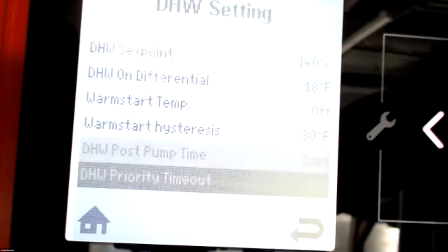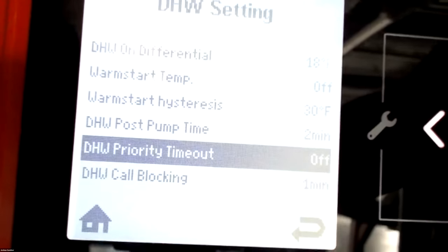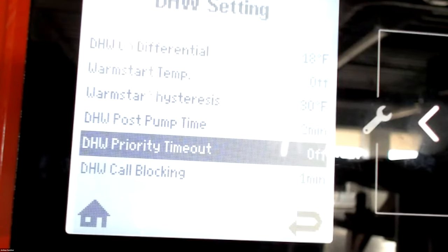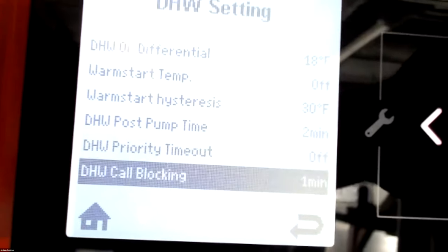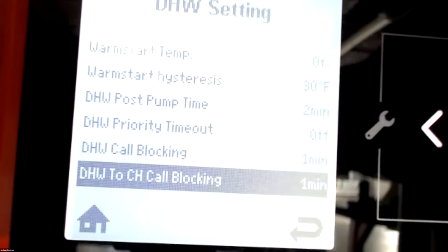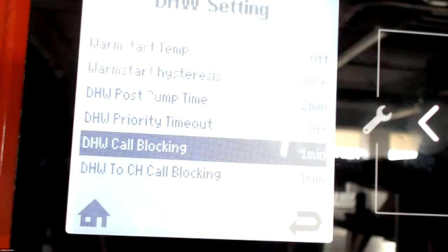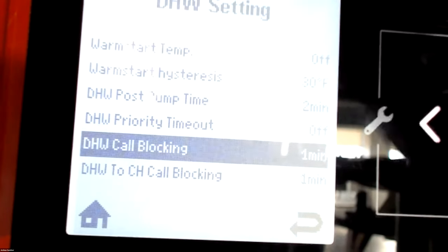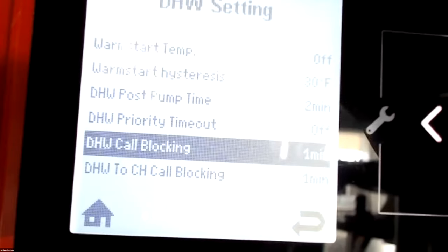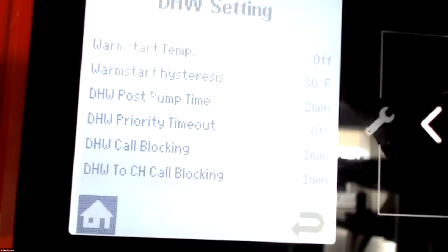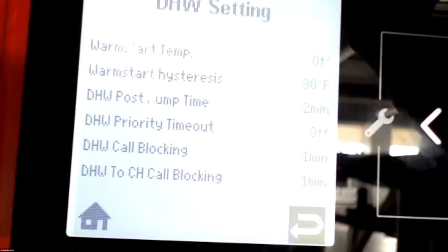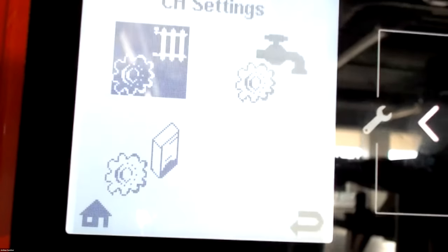DHW post pump time, priority, timeout, so we can turn that off. So if your indirect's calling for long periods of time, or you have, you know, teenage girls, you can have this shut down at a certain predetermined time so it doesn't call constantly and prevent the heat from kicking on. And then your DHW call blocking for, you know, DHW calls if you didn't want to go back to back. And then our DHW to CH call blocking from the central heating call to DHW call. And that's DHW settings.